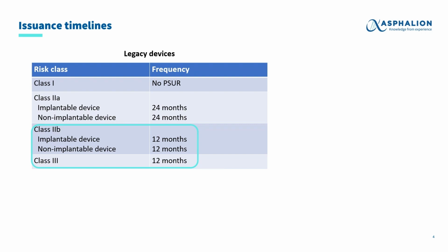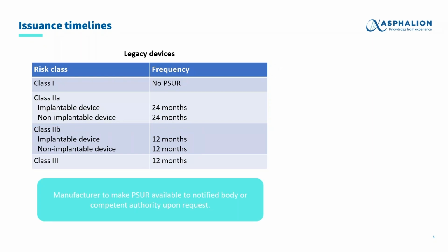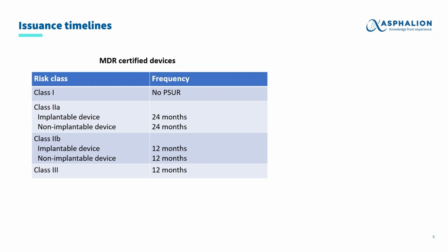Focusing now only on legacy devices, which are those that are on the market but certified under the old directive, for this kind of PSURs, manufacturers should make the PSUR available to notified body and competent authorities only upon request. On the other hand, for MDR compliant devices, the frequency for issuing the PSURs is the same as for the legacy devices. That means every 2 years for Class 2A medical devices and at least annually for Class 2B and Class 3 medical devices.